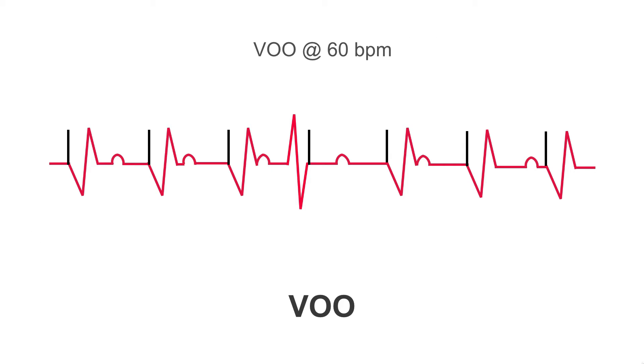Let's have a look at VOO in action. The first thing to notice is that on this electrogram we have P waves and QRS complexes, and there is no relationship between the two. Remember, the pacemaker isn't sensing, so there's no way it can ensure synchronisation of the atrial and ventricular events. We can see output pulses triggering ventricular depolarisation here, here, and once more here.